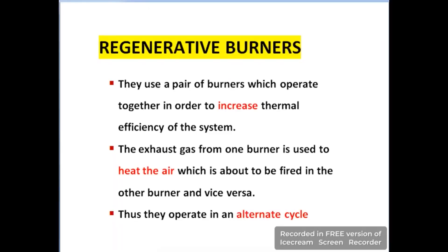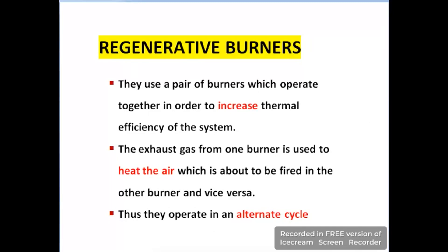The second type of burner is the regenerative burner. These types of burners contain a pair of burners and both operate together. The purpose is to increase the thermal efficiency of the system. The exhaust gas from one burner is used to heat the air which is about to be fired in the other burner. It is a pre-treatment process where air drawn from the atmosphere is preheated with the exhaust gas. They operate in an alternate cycle.